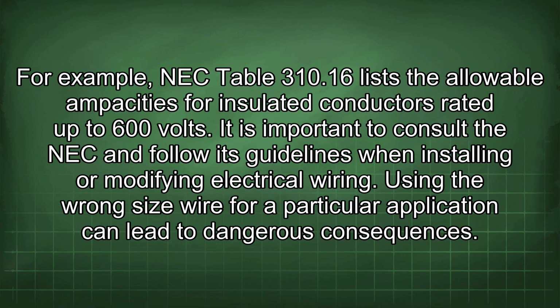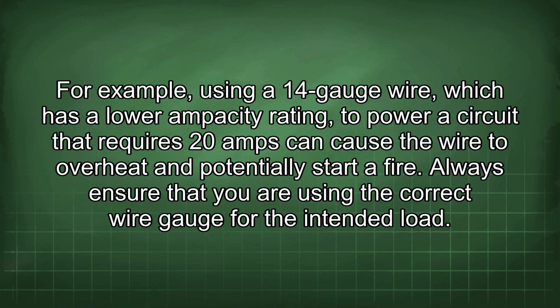It is important to consult the NEC and follow its guidelines when installing or modifying electrical wiring. Using the wrong size wire for a particular application can lead to dangerous consequences. For example, using a 14-gauge wire, which has a lower ampacity rating, to power a circuit that requires 20 amps can cause the wire to overheat and potentially start a fire. Always ensure that you are using the correct wire gauge for the intended load.